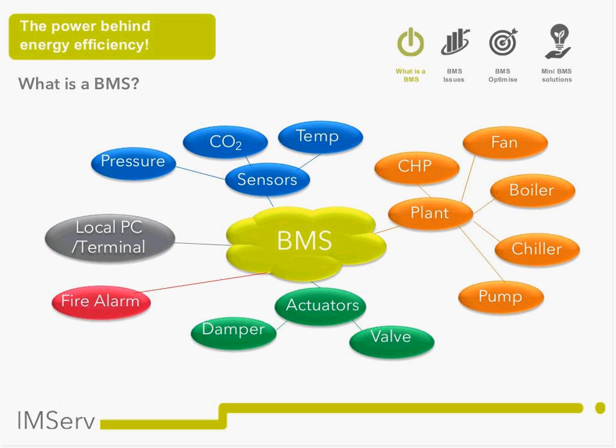Air handling systems are also linked to the building management system. They are effectively a standalone heating and cooling system, but they do benefit from working in harmony with other systems in the building rather than fighting against them. The actuators control the flow of water and air throughout the building. Valves control the flow of hot and chilled water, and dampers control the flow of air. The actuators enable the BMS to direct the hot and chilled water to zones where they're required. You can get simultaneous heating and cooling demands even in the same building.